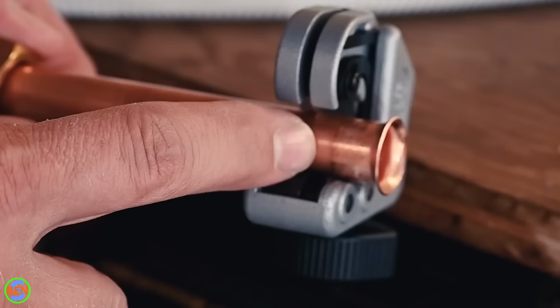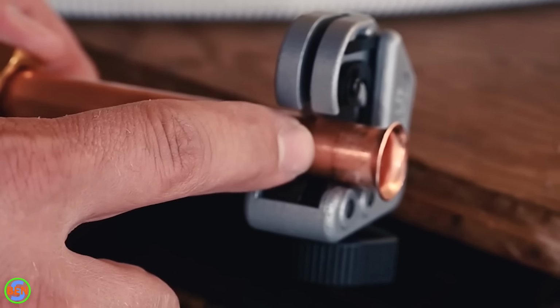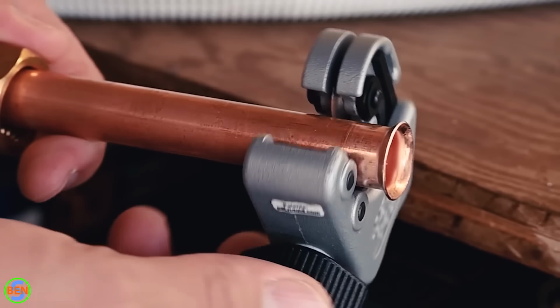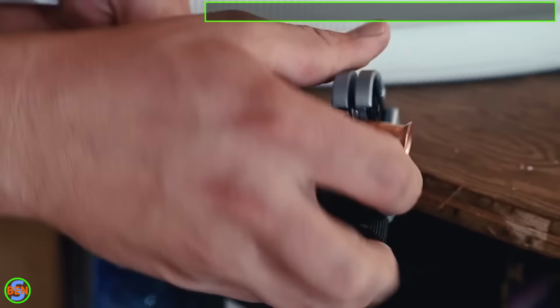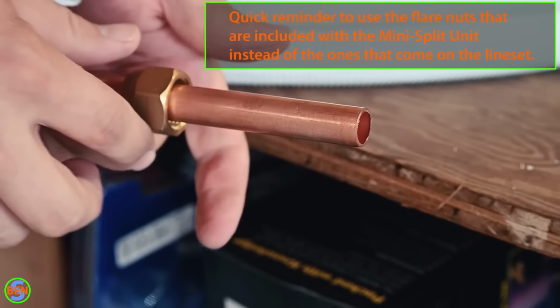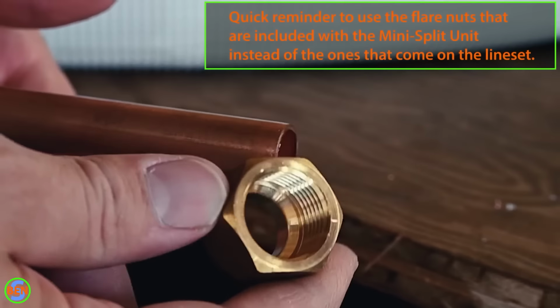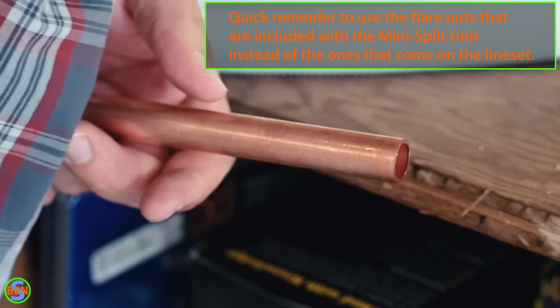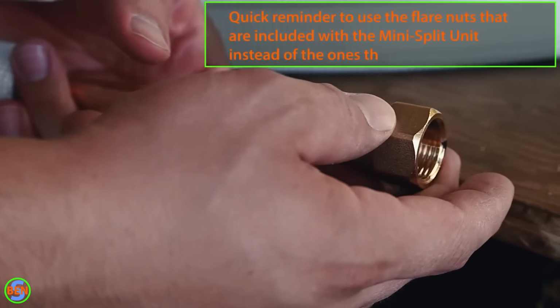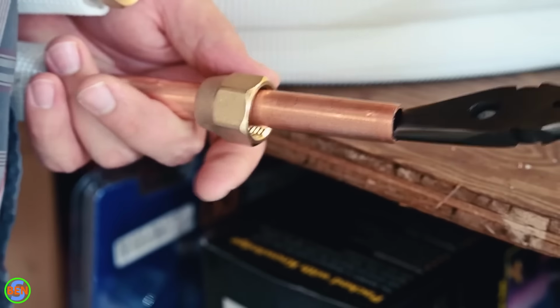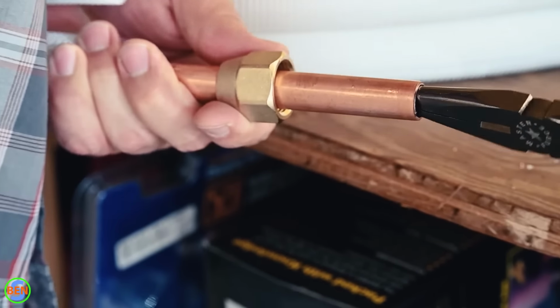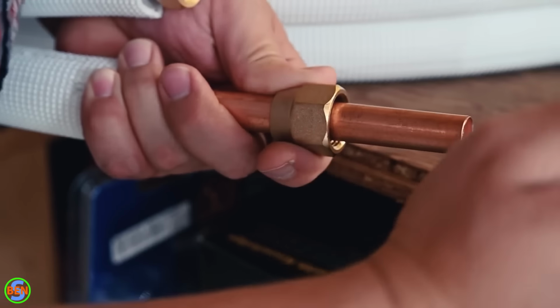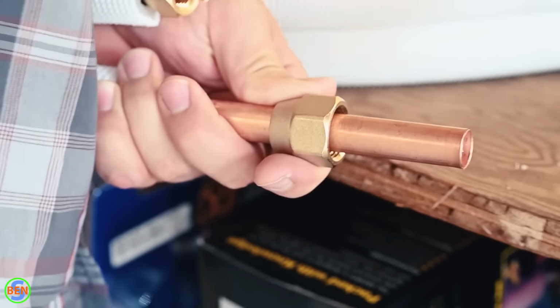Take our tubing cutter and cut back just far enough that we're past where the previous die had squeezed down onto the copper. We're going to take off our factory flare nut that came on this line set and replace it with the nut that came with the mini split. And take our needle nose and ream out the inside. That's adequate, and I can feel this with my pinky. Make sure that there's no burr left.